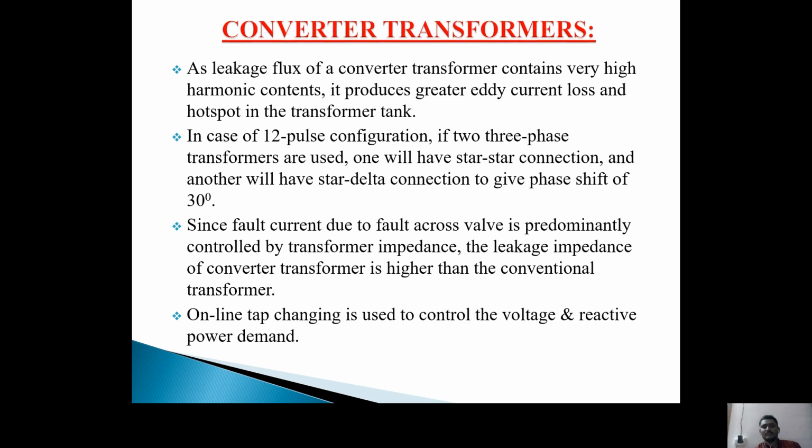In case of a 12-pulse configuration, if two 3-phase transformers are used, one will have a star-to-star connection and the other will have a star-to-delta connection to give a phase shift of 30 degrees. I already discussed this point in the previous section.